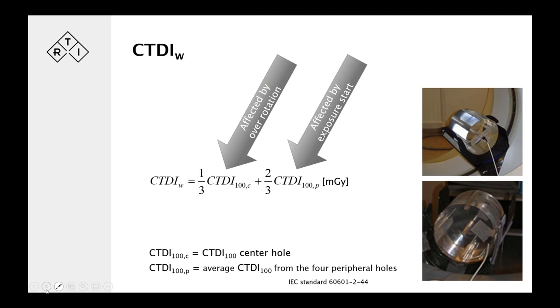So there we've got an additional contribution of 4.5%, even up to 13.5% for the center hole. Of course, if we add up and do all the math, we're still maybe at 20% off between two CTDI weighted measurements, where we have the pass-fail limits typically at ±20. So we're pushing the limits here a little bit when looking at this kind of thing.